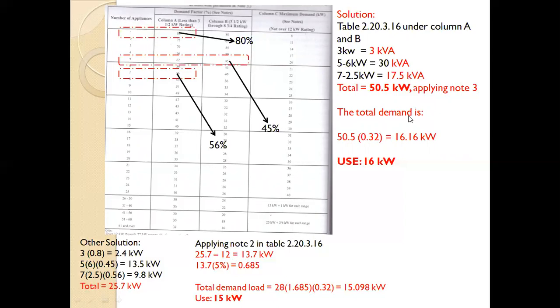Applying note 3, please check your PEC and read note 3 there. The total demand of 50.5 times 0.32 gives a total demand of 16.16 kilowatt. So use a 16 kilowatt load. This solution is also possible.